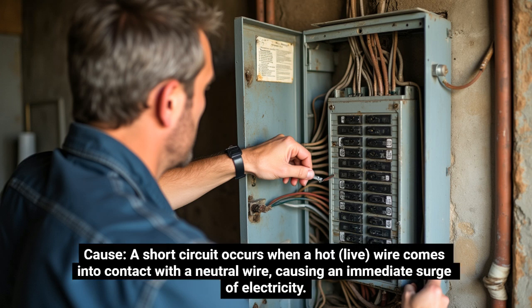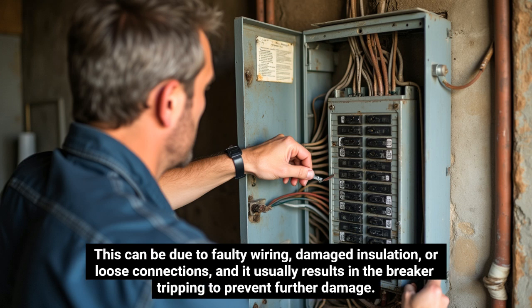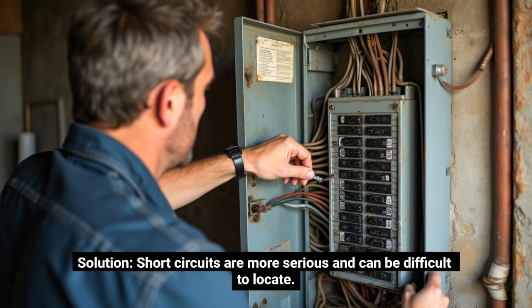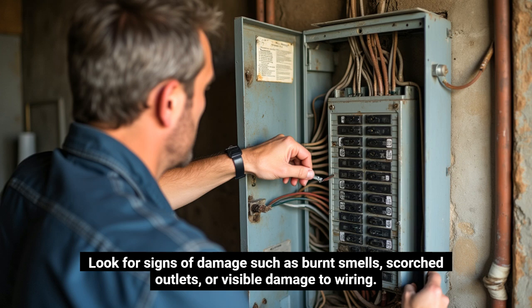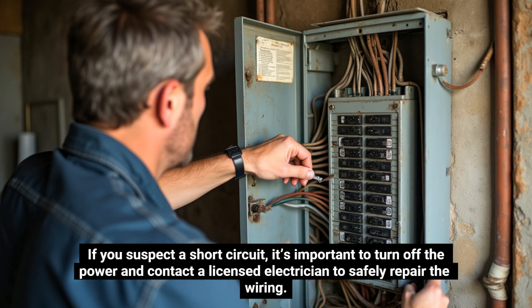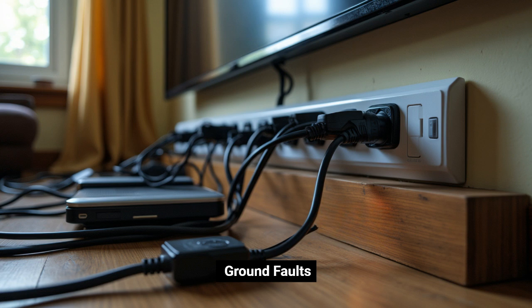Cause: a short circuit occurs when a hot, live wire comes into contact with a neutral wire, causing an immediate surge of electricity. This can be due to faulty wiring, damaged insulation, or loose connections, and it usually results in the breaker tripping to prevent further damage. Solution: short circuits are more serious and can be difficult to locate. Look for signs of damage such as burnt smells, scorched outlets, or visible damage to wiring. If you suspect a short circuit, it's important to turn off the power and contact a licensed electrician to safely repair the wiring. Ground faults.